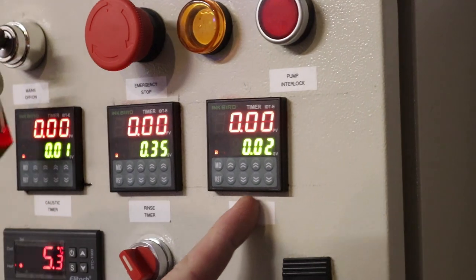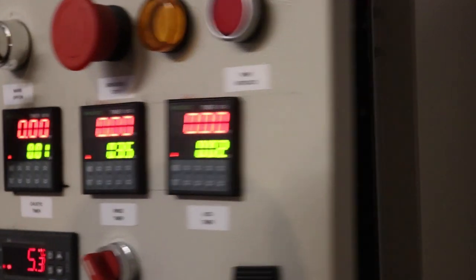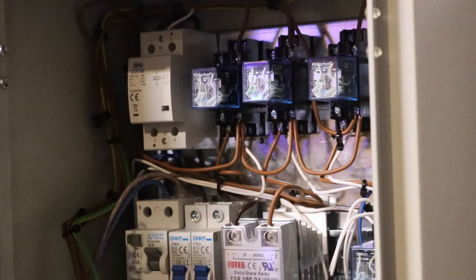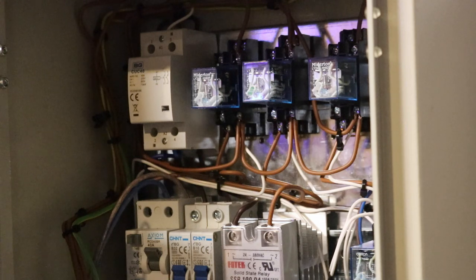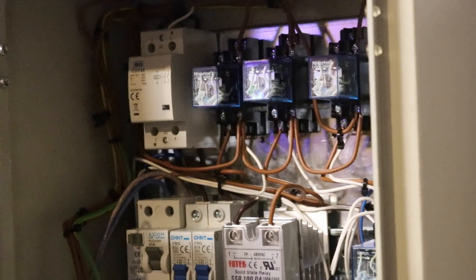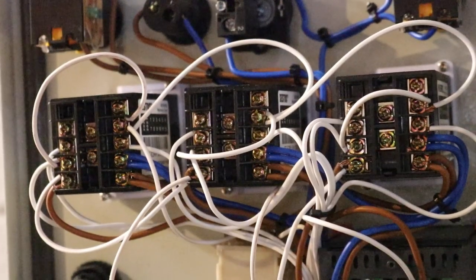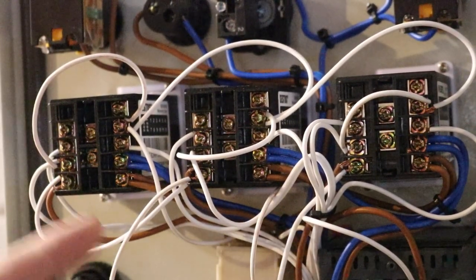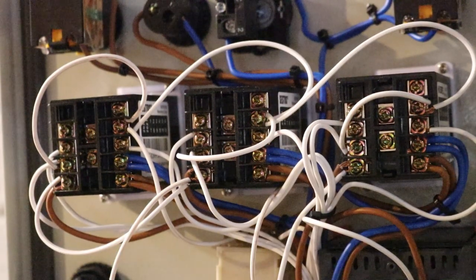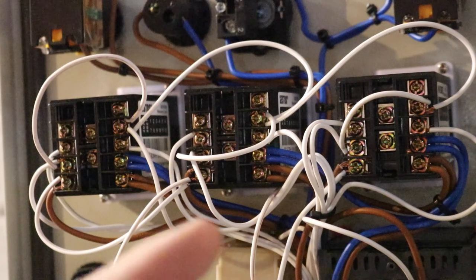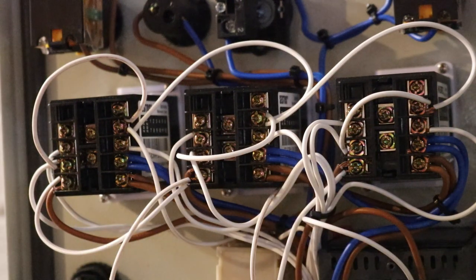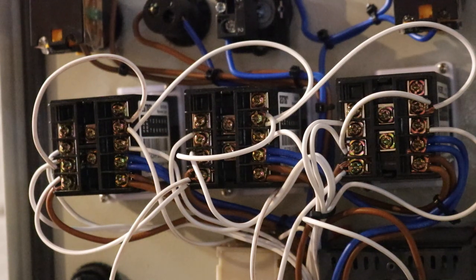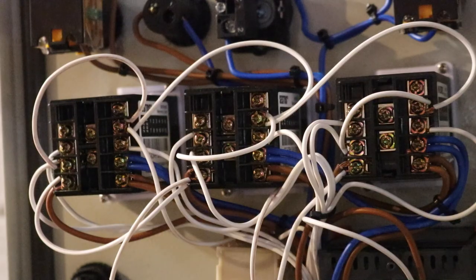That seems to be a much cleaner 12 volt signal than what's being put out by the timers. Unfortunately these outputs are no good for switching something like this. So what we've had to do is we've also taken that 12 volt supply and we've run that through the back of all these relays, sorry timers. We've run that 12 volt signal through the back of all these timers and use the normally open contacts to provide a signal to the mechanical contactors so we can switch the pump on and off.